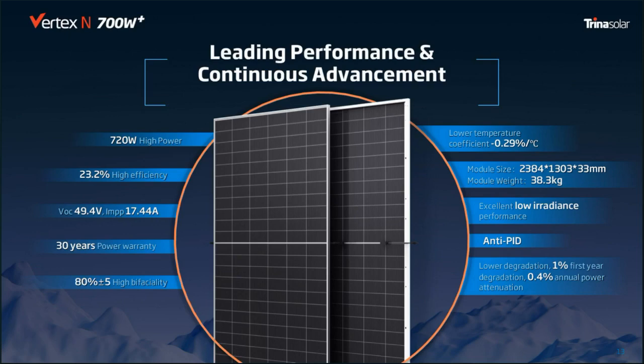Thanks to these technological advancements, our modules can achieve 720 watts power and 23.2% efficiency, with a 30-year warranty, up to 85% bifaciality, a lower temperature coefficient of 0.29% per degree, and our standard large format dimensions of 2384 by 1303 millimeters. They also feature improved low irradiance performance, PID resistance, and lower initial and annual degradation rates.